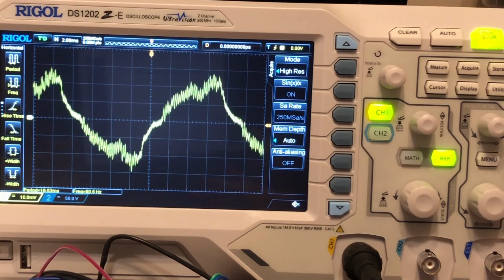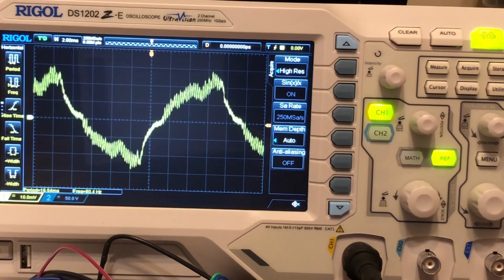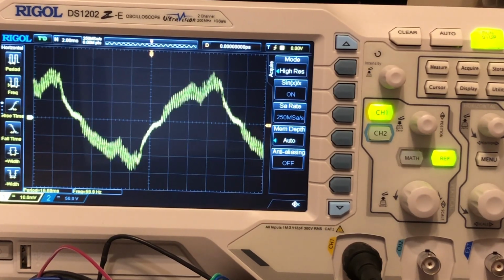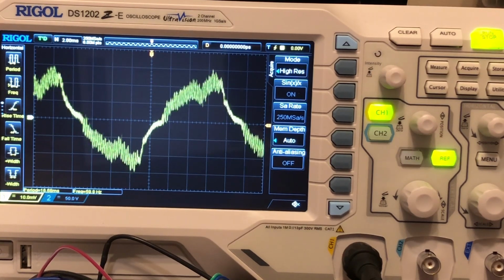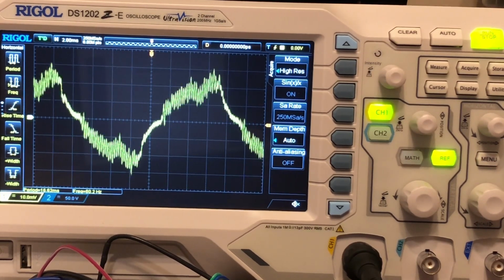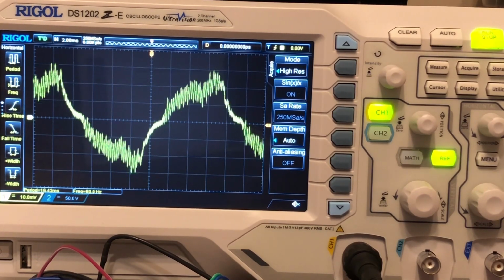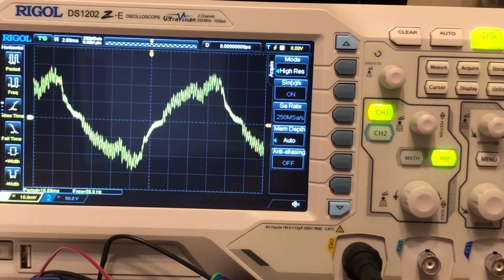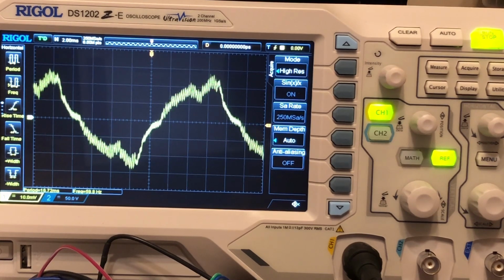Chapter 5, to trigger the oscilloscope. As for trigger, you can set certain trigger conditions according to the requirement, and when a waveform in the waveform stream meets this condition, the oscilloscope captures this waveform as well as the neighboring part and displays them on screen. For a digital oscilloscope, it samples waveform continuously no matter whether it is stably triggered, but only stable trigger can ensure stable display. The trigger module ensures that every time base sweep or acquisition starts from the user-defined trigger condition. Namely, every sweep is synchronous to the acquisition and waveforms acquired overlap to display a stable waveform.